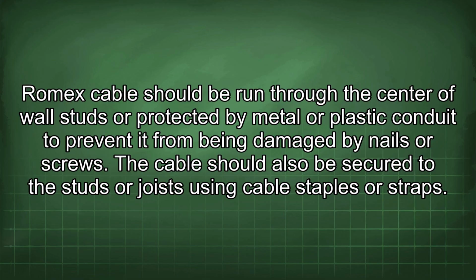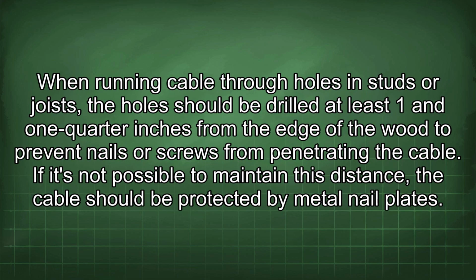The cable should also be secured to the studs or joists using cable staples or straps. When running cable through holes in studs or joists, the holes should be drilled at least 1 1/4 inches from the edge of the wood to prevent nails or screws from penetrating the cable. If it's not possible to maintain this distance, the cable should be protected by metal nail plates.